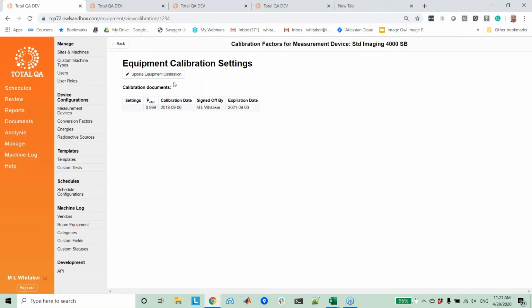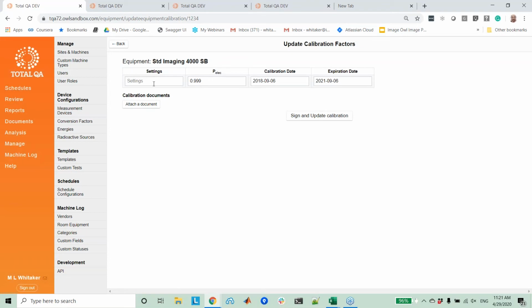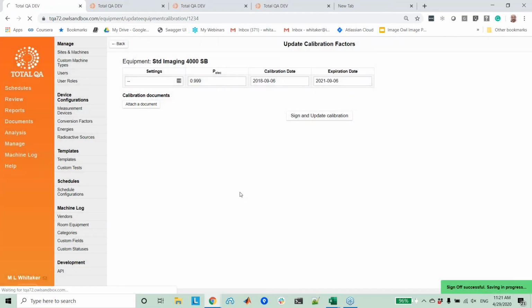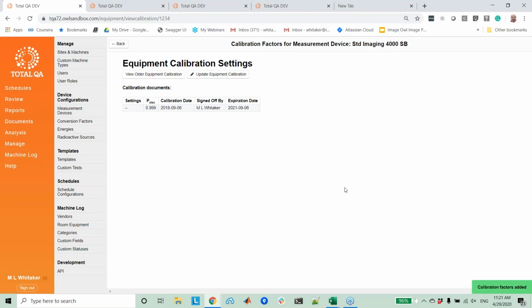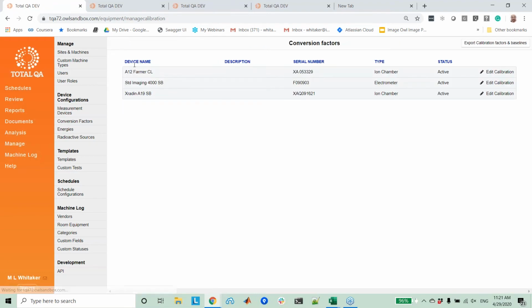electrometer, and really all you're putting in there is any settings for that electrometer. So if there are standard setup settings that you wanted to make sure it was set to when you're doing your TG51, note those there, and your electrometer factor. So if I'm going to make those changes, I've now signed off on it, and it's updated, and that'll be recorded in the system.